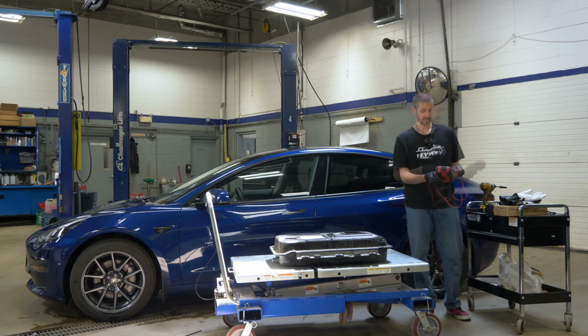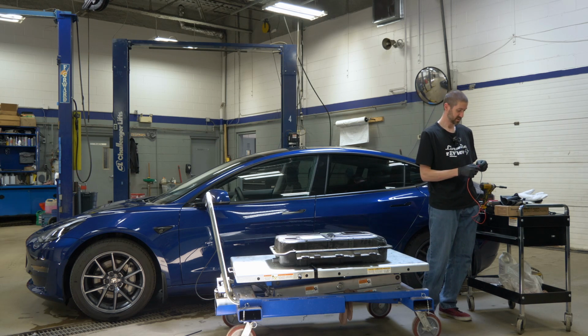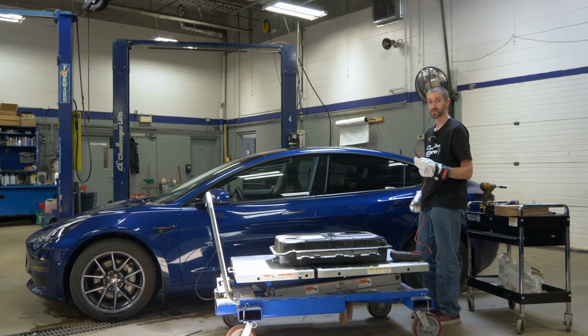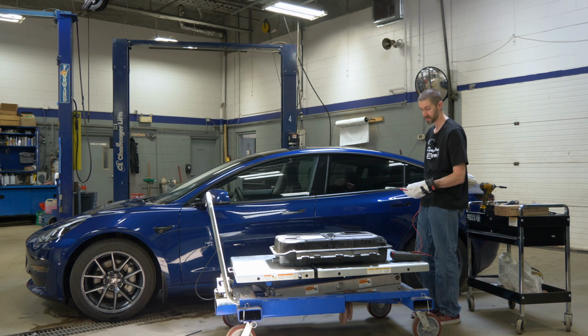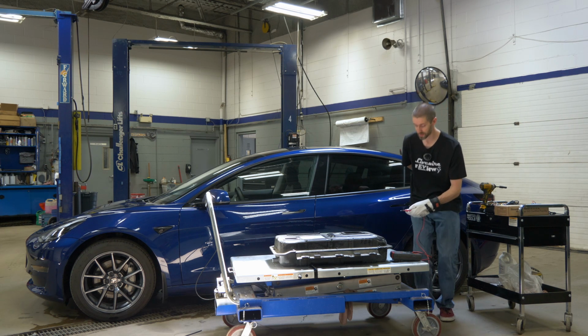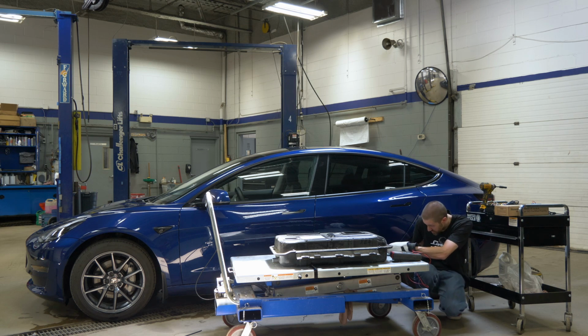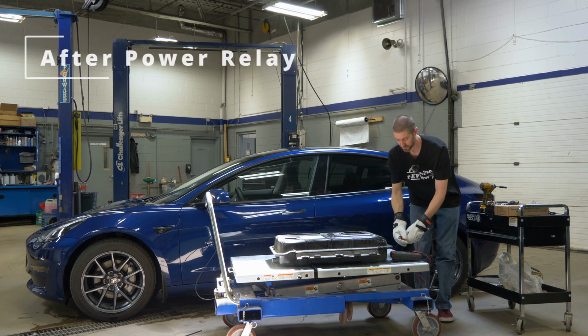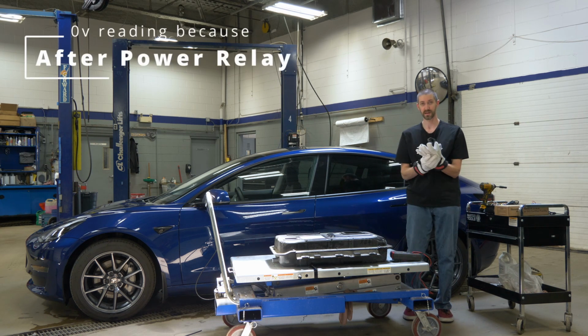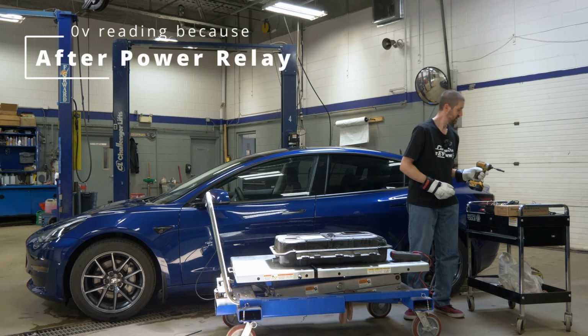Set to voltage. We're going to test the leads themselves, make sure they're working, read 0 volts. Excellent. So the one-handed rule makes this difficult to get these readings. You've got to set your meters apart here and try to take this reading with one hand. So I'm going to reach right in here and see if I can get a reading across these terminals. I am actually reading 0 volts across these terminals, so it looks like we may have disabled this already. So it's time to open up the case and see what's inside.